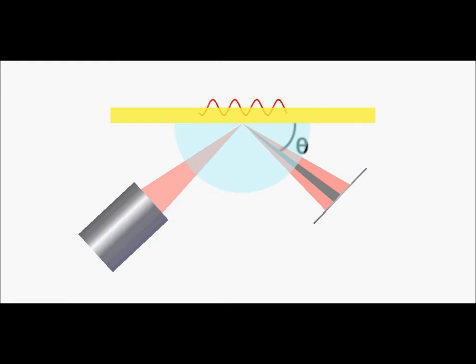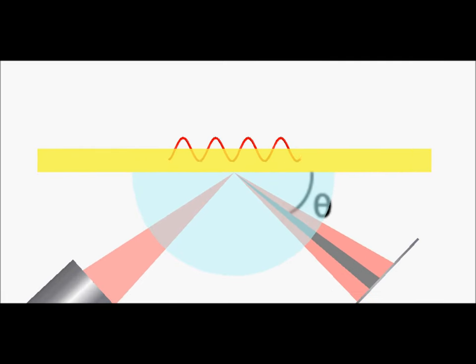At a certain incident angle, known as the resonance angle, light is absorbed by the electrons in the metal film of the sensor chip, causing them to resonate. These resonating electrons are also known as surface plasmons, which are sensitive to the surrounding environment.